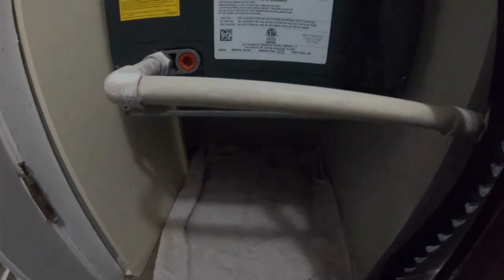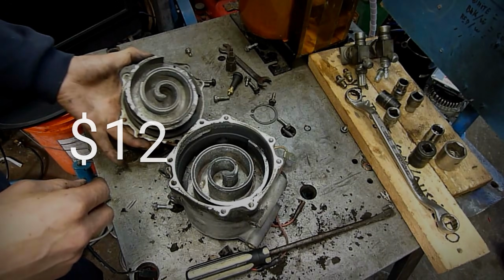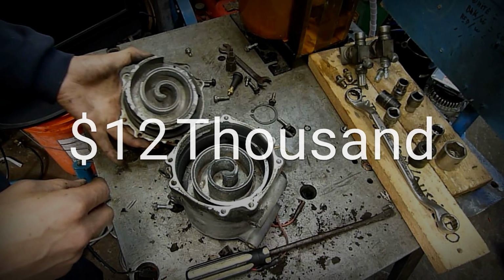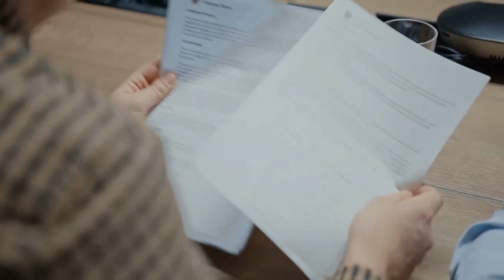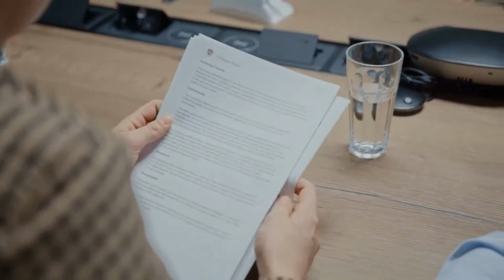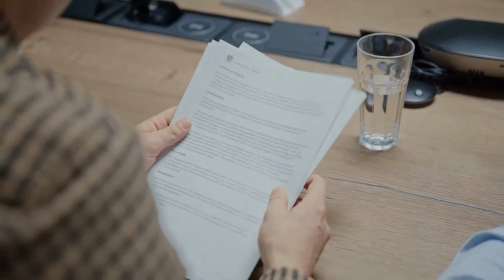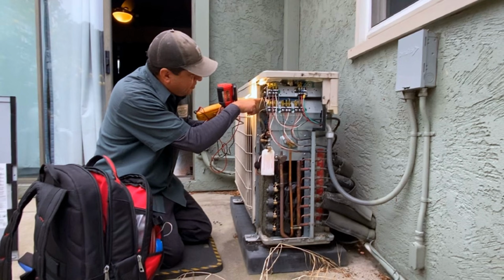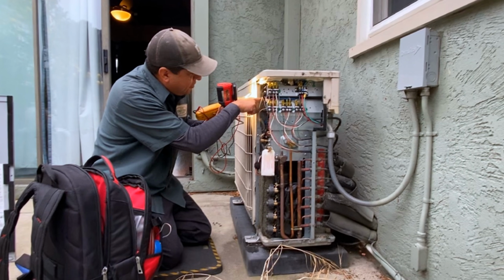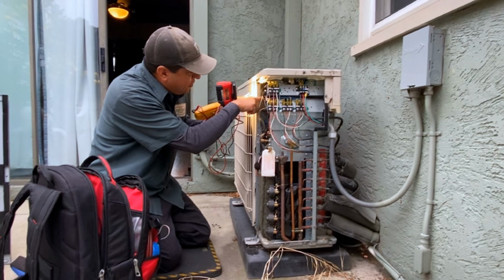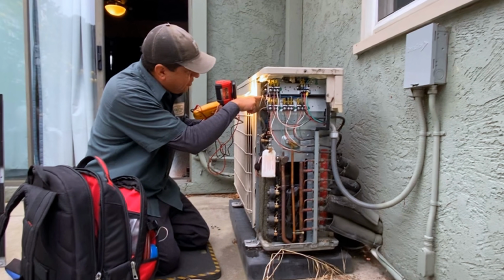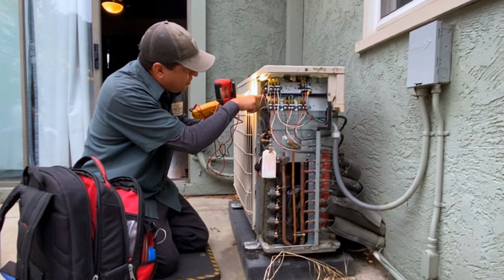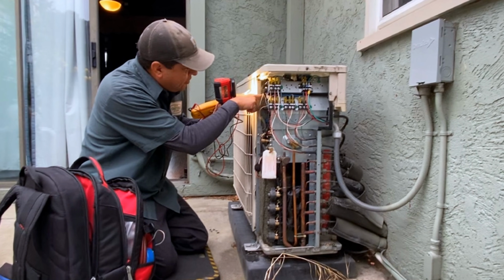You now have ice inside your air handler, a compressor running against a starved load, and a $5,000 to $12,000 catastrophic failure approaching somewhere between year 8 and year 12. Meanwhile, your builder's warranty, typically 2 years on mechanical systems, expired in year 2. The manufacturer's warranty covers the parts, not the labor, not the refrigerant recovery charge, not the crane fee if your condenser is on the roof, not the disposal of the old equipment.